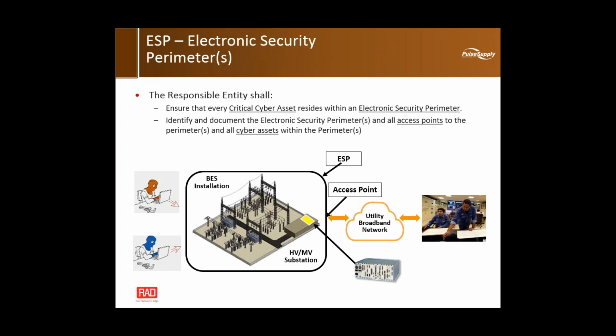So ESP, the electronic security perimeter—I like to define it as an imaginary fence. All the devices considered cyber assets or cyber systems sit inside this electronic security perimeter. It has access points, and it could be a single access point or multiple access points depending on how the networks are configured or how they communicate to an electronic substation. Essentially, NERC says that the responsible entity shall ensure that every critical cyber asset resides inside an ESP, and then they have to identify and document the electronic security perimeter, all the access points to it, and all the cyber assets inside the perimeter.